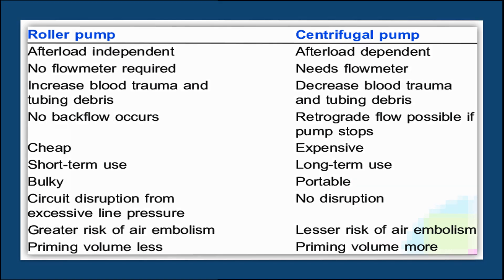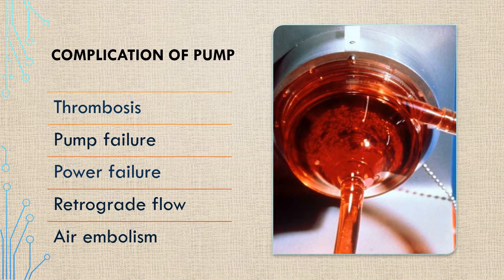The centrifugal pump is afterload dependent, so a flow meter is needed. Retrograde flow will occur if the pump stops, as it is a non-occlusive pump. It is intended for long-term use and is portable, but expensive.